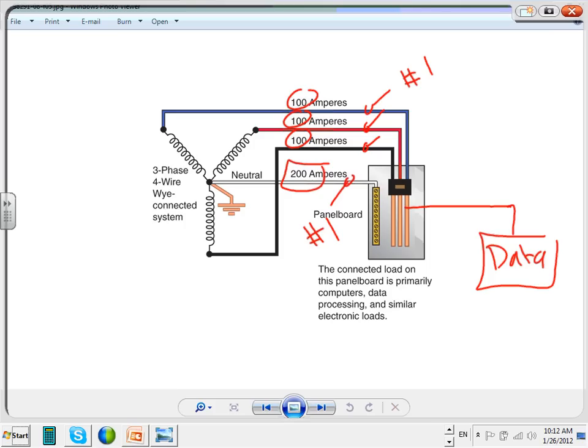You burn that baby. In a data center, guys, they size the neutral double the phases. So for 200 amp double, now you go into the 75 column because it's higher, you need 3 aught. So the neutral here will be 3 aught. We have a double neutral conductor size. Why? Because of the harmonics, the third harmonic especially adds up on the neutral.